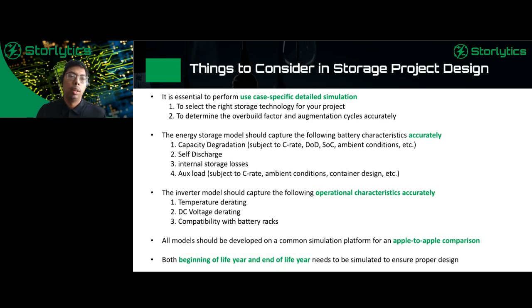Self-discharge needs to be modeled correctly. You need internal storage losses, like RTE losses, which vary over time and over your SOC range, and you need to capture that. Your auxiliary load assumptions vary with C rate, temperature, and container design, liquid cooling versus air cooling. All these factors play into auxiliary load assumptions, so you need an accurate, validated model to come up with good design assumptions.